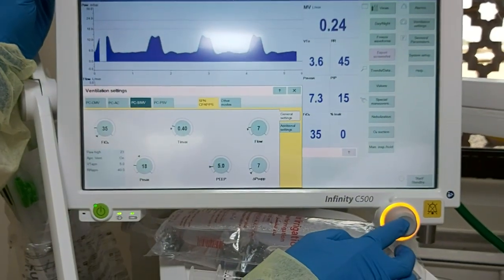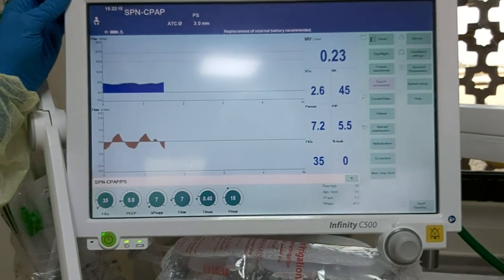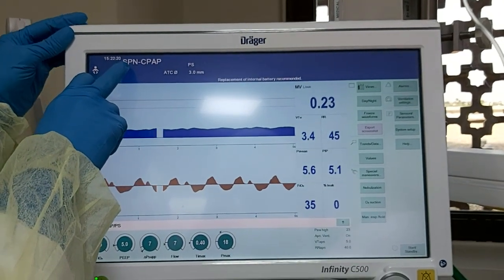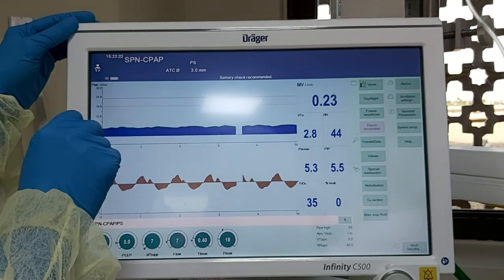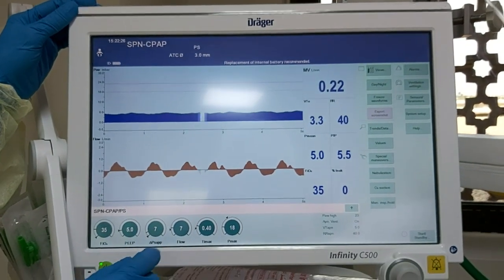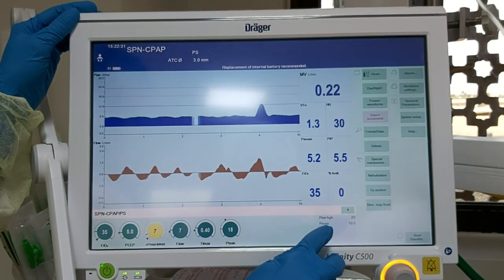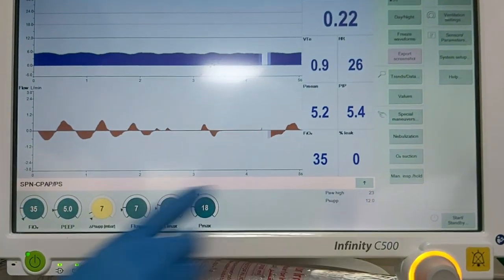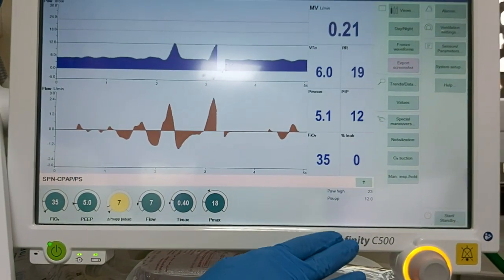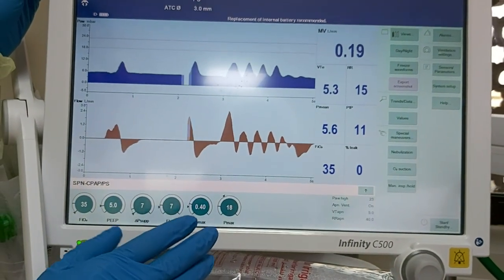Confirm the mode. Now it's giving us spontaneous breathing — spontaneous mode, CPAP pressure support. Here you can see FiO2, PEEP, and pressure support displayed. If you press on top of pressure support, it will give you the total pressure support of 12 — 7 plus 5 is 12. So it is delivering 12 cmH2O pressure support to the baby. After shifting the mode to pressure support ventilation, you have to monitor and observe the spontaneous measured values from the baby.